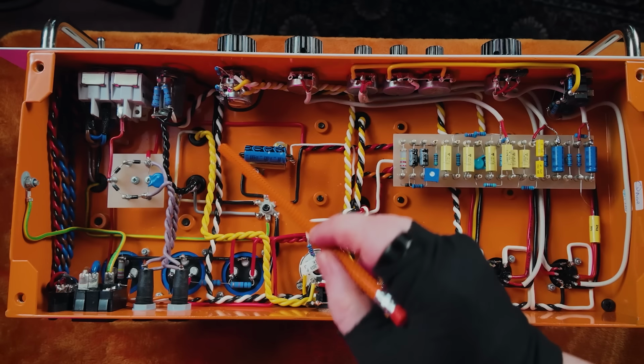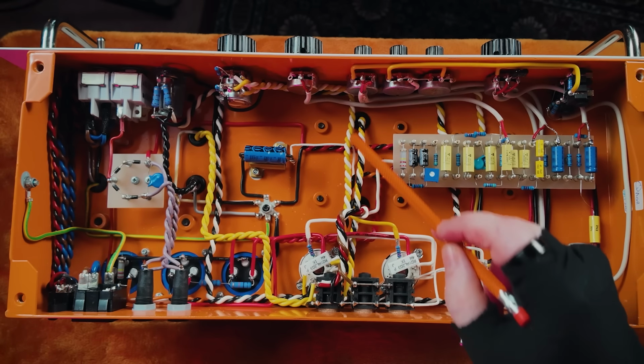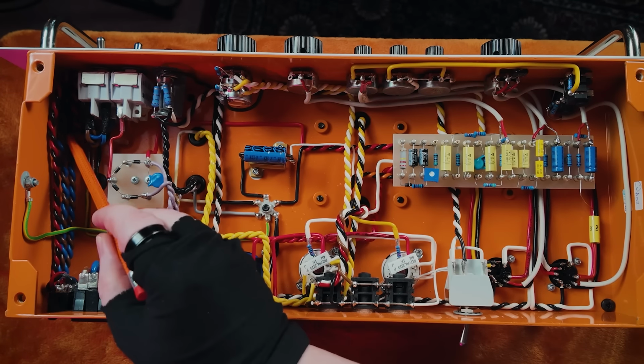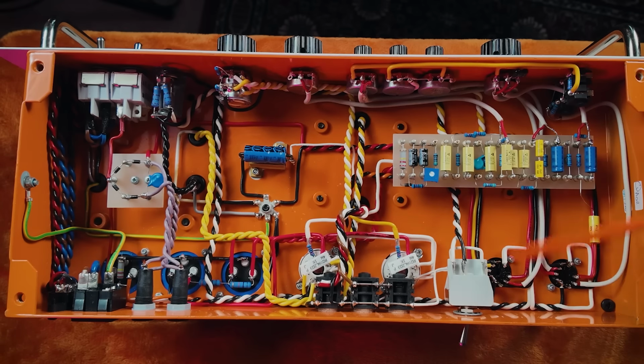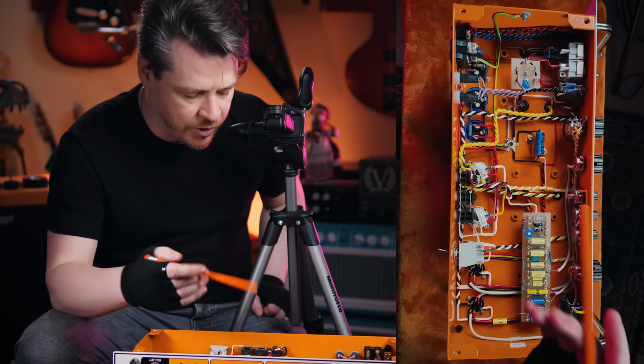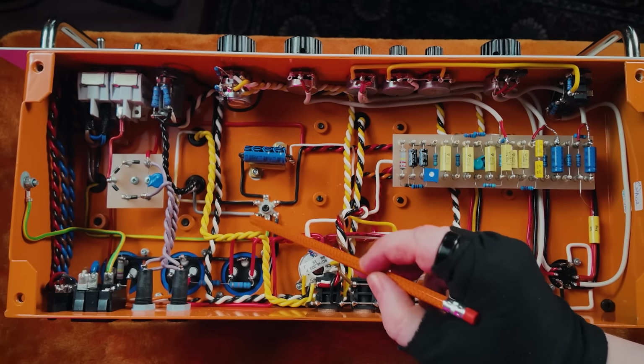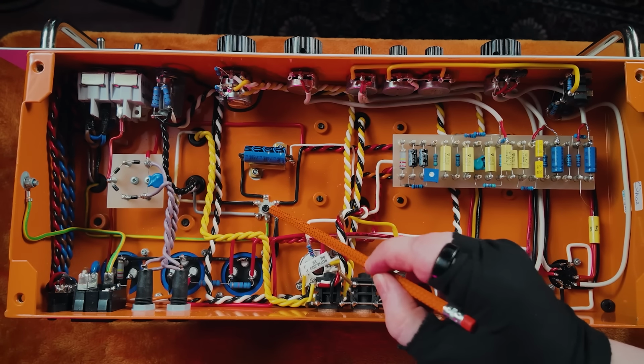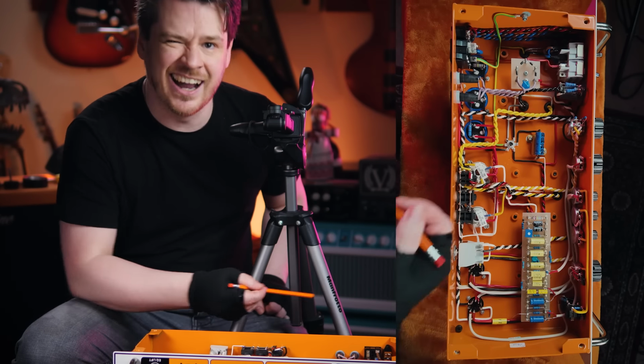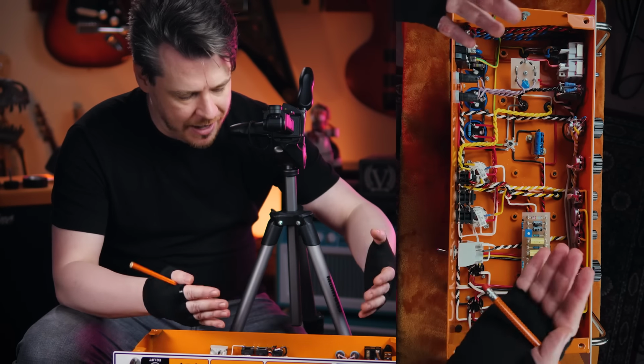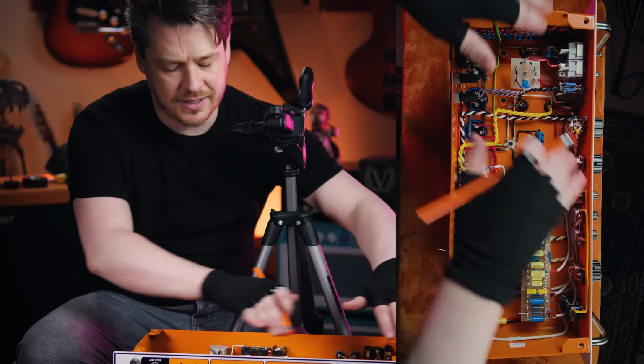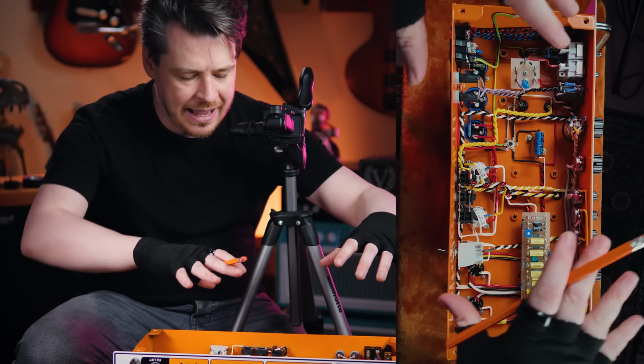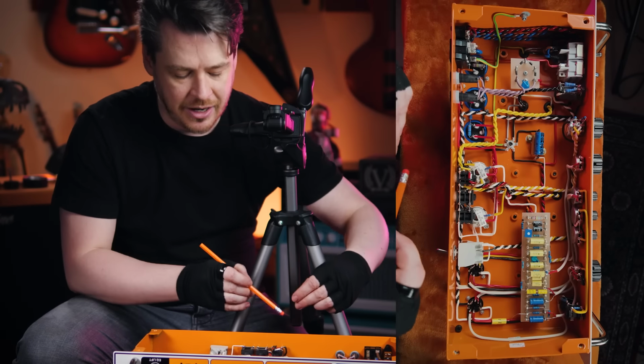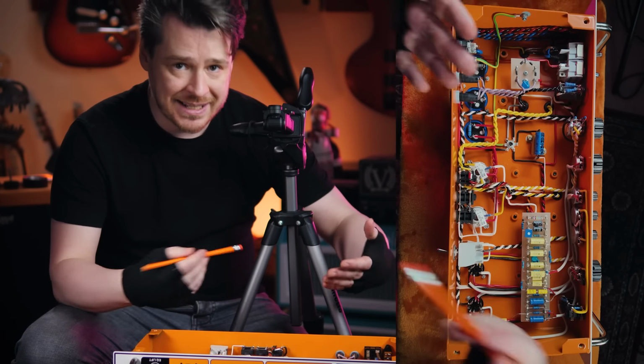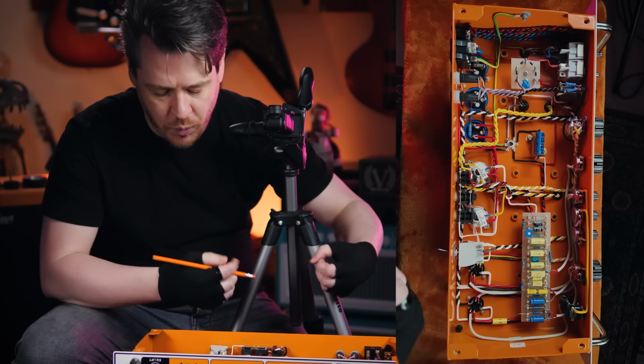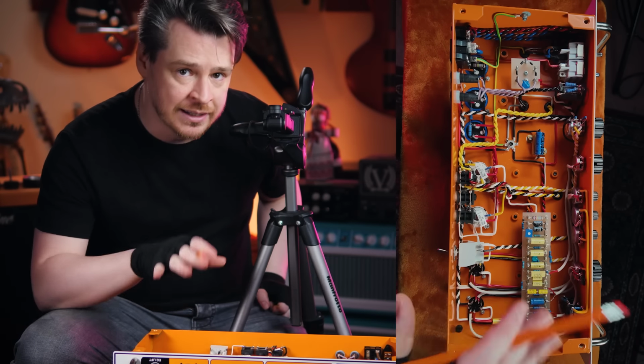We also see that all of these twisted pairs are trying to run as close to the chassis as possible, including into the corners of the chassis, because the chassis acts as a ground plane. There's a star point where all the different grounds come to one point on the chassis, and that gets carried away to ground. So the big power wires that generate electric fields are tucked into the corners of the chassis, helping those fields get sucked away to ground via the ground plane. That's an effort to take the electric fields away before they can affect any of the weak signal wires.